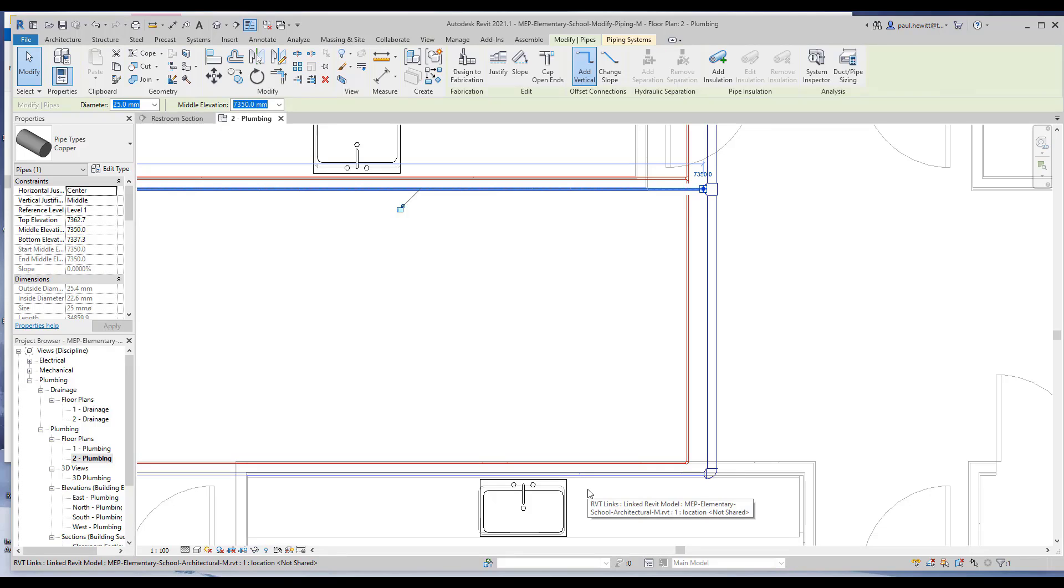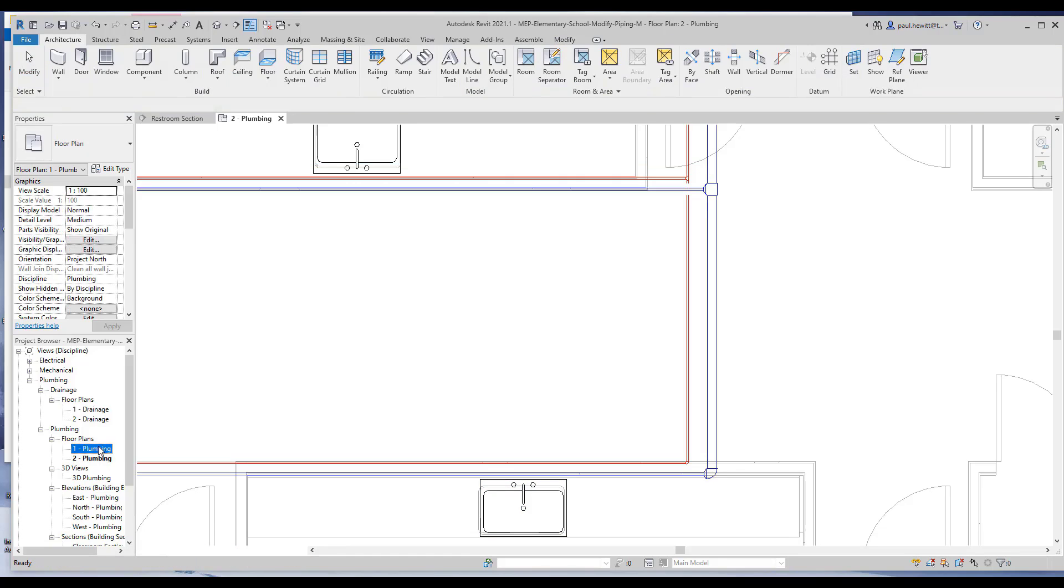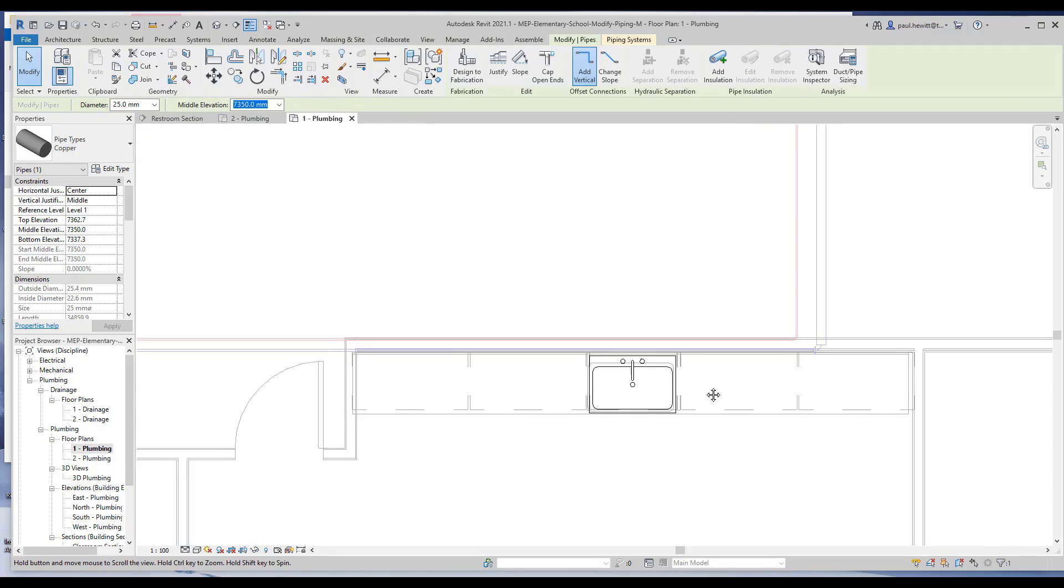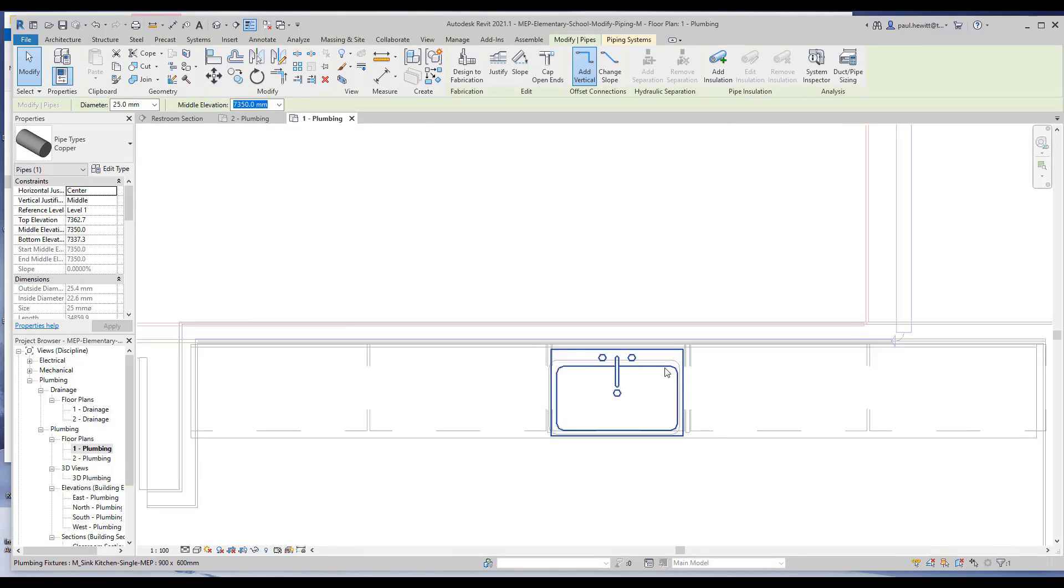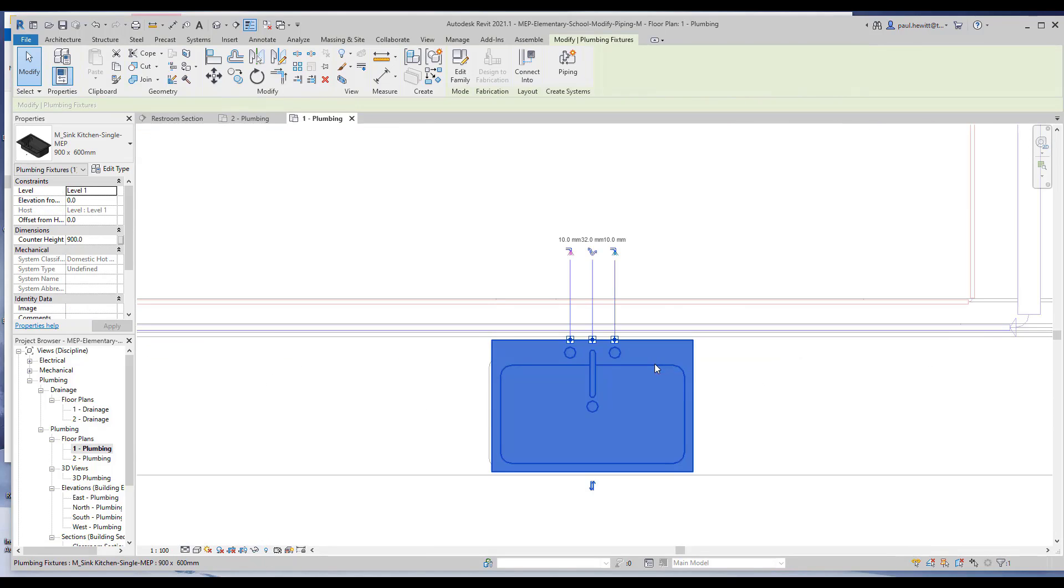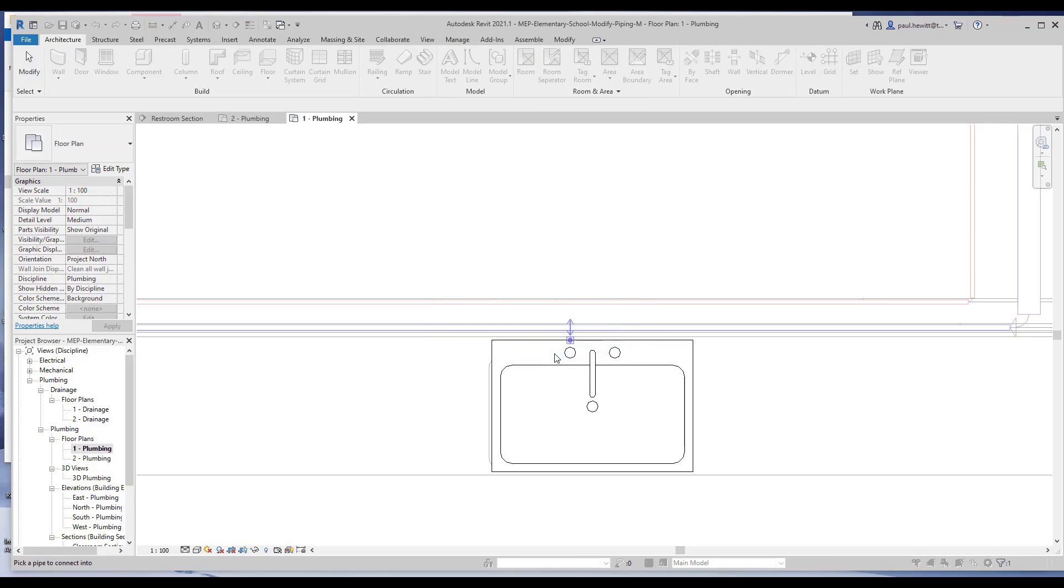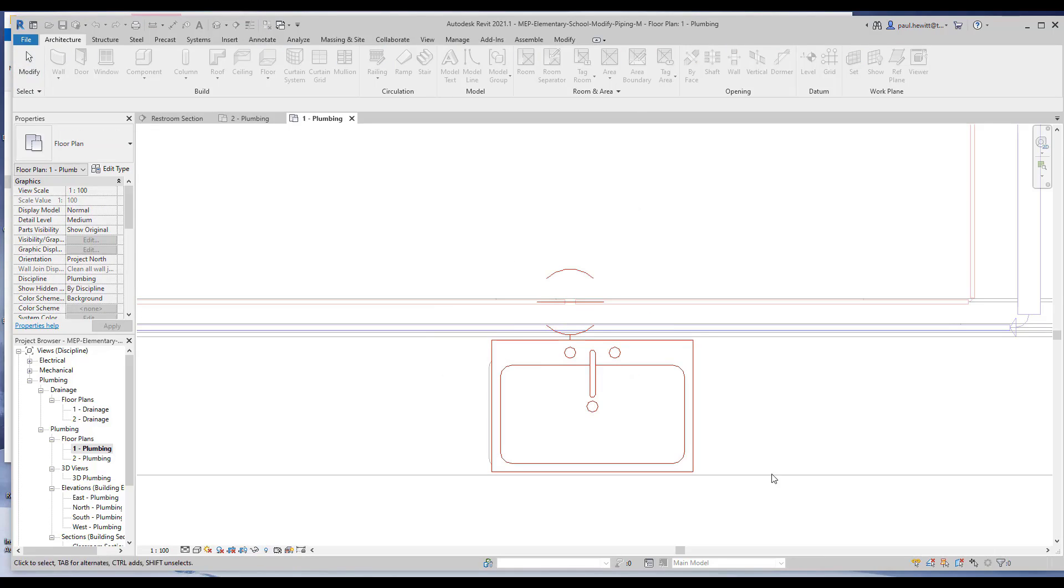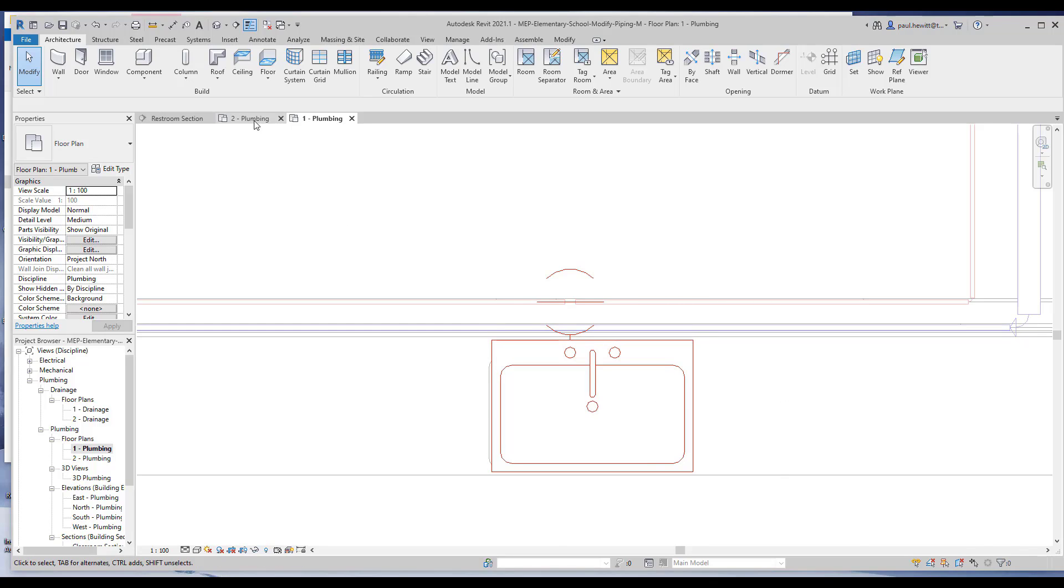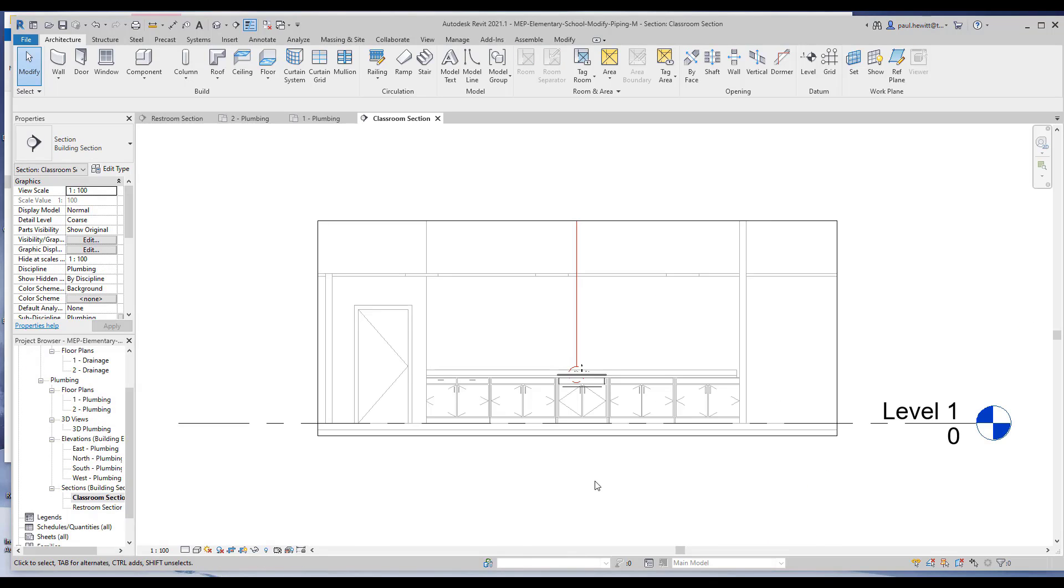So the next thing I need to do is connect these sinks in. So one way I can do this is selecting that particular sink. Let's do this in the lower level. So select my sink. And I've got my connect into option. We'll do the hot water in this case. All I do is go OK and then select the hot water piping that we need to connect into. I could do this again with the cold water. Or what I could do is actually go back to a section that I've already selected. And I can draw it in a section.